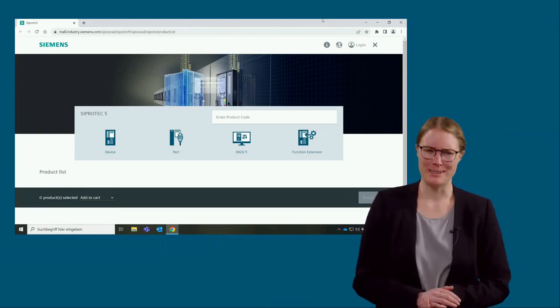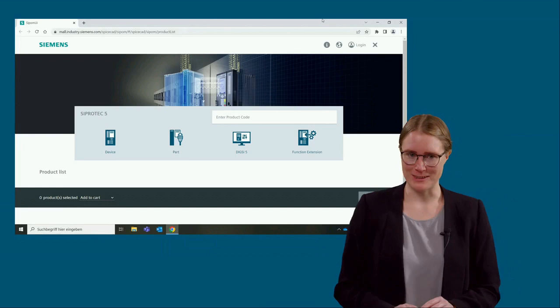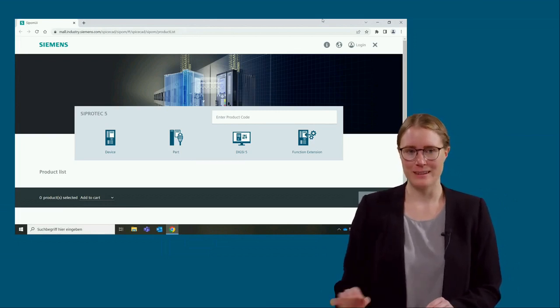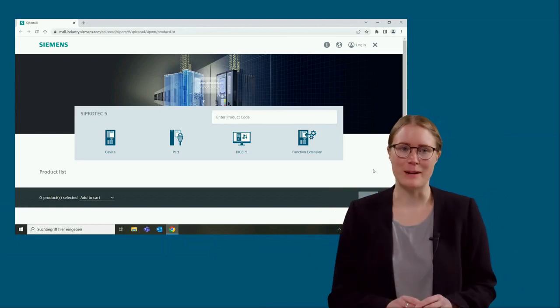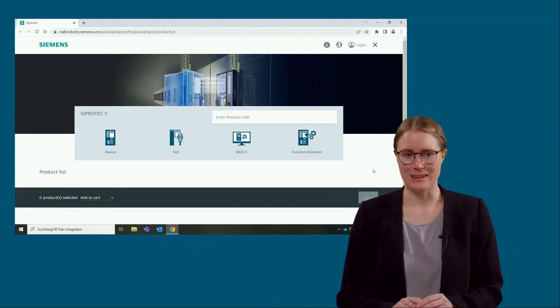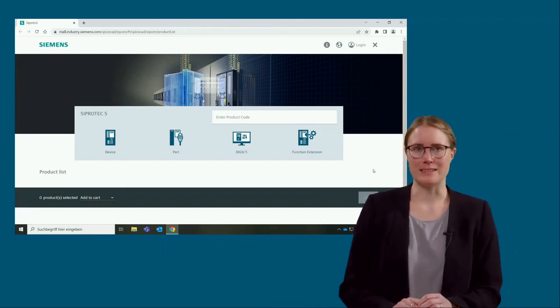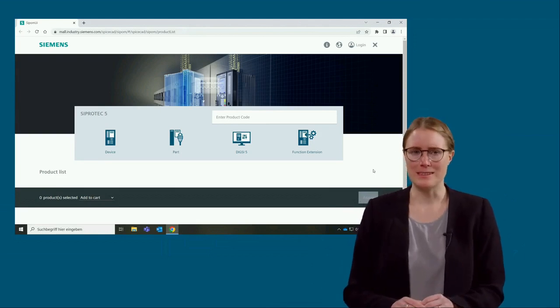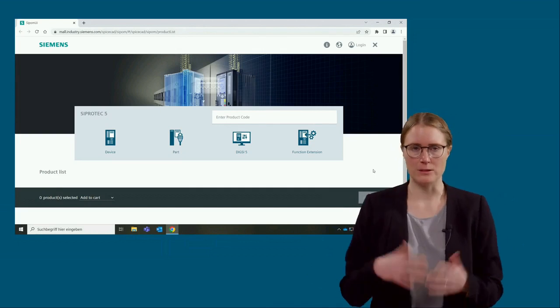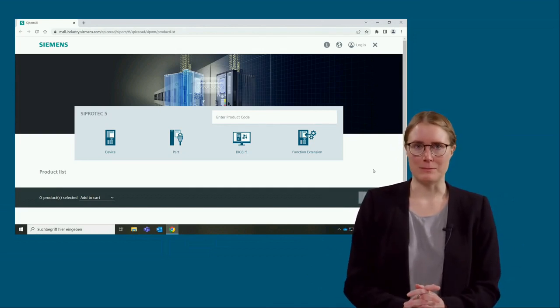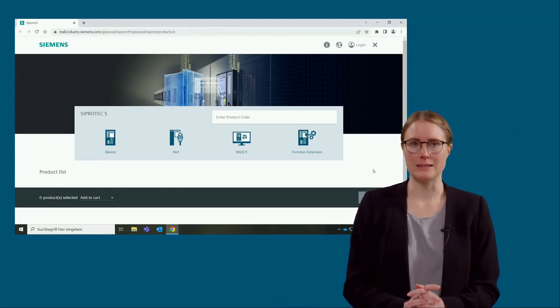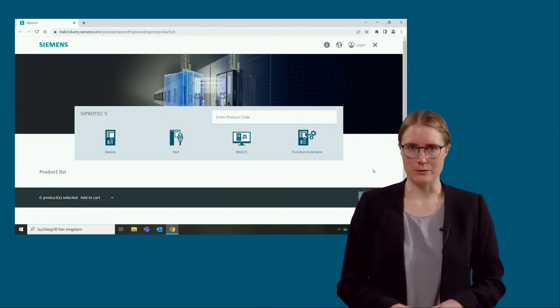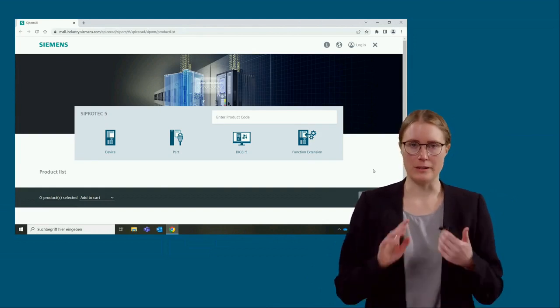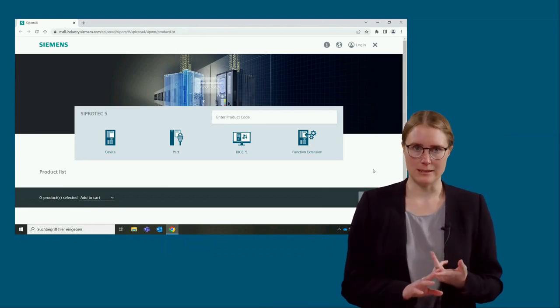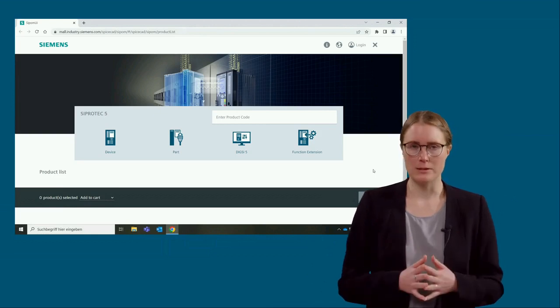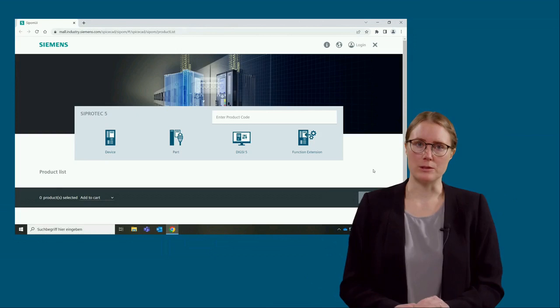So in the last 30 minutes of this tutorial, I want to give you a short demonstration of our SIPROTEC 5 configurator. I want to just remind you shortly of the example Rainer demonstrated earlier. He explained an example of a double busbar system with 4 feeder bays and 1 coupler bay, so 5 bays in total. For this setup, the disconnector image was needed. And I want to show you how to select the devices for this setup for a centralized busbar protection, for an IEC 61850 compliant solution in a fully distributed setup, and for the 7SS85 CU solution.